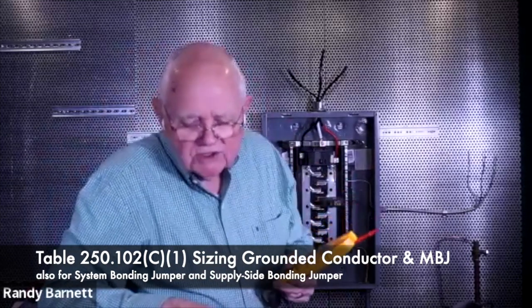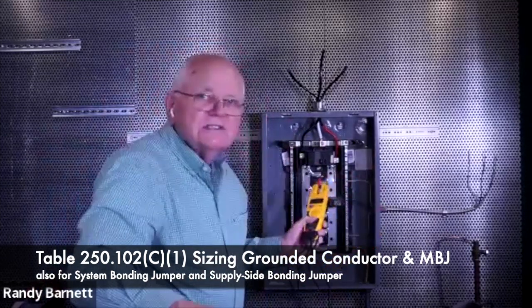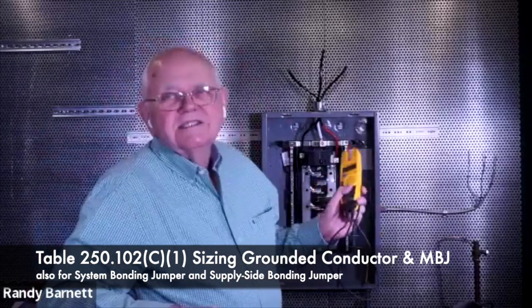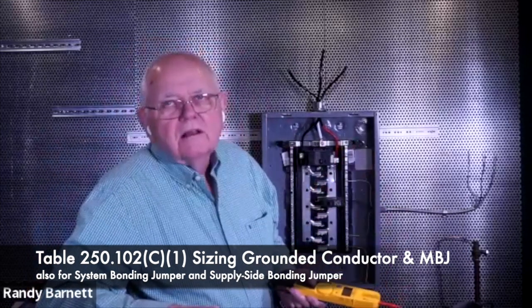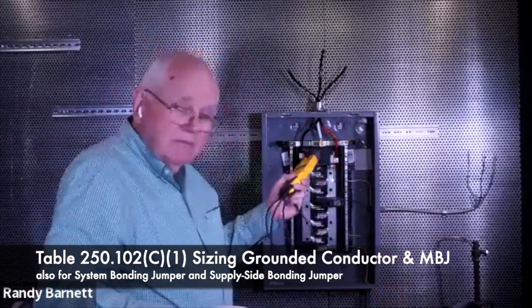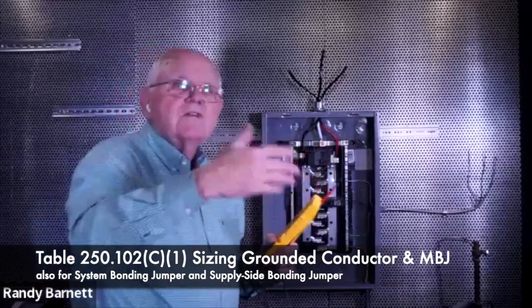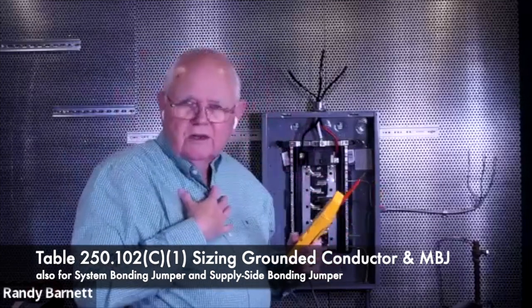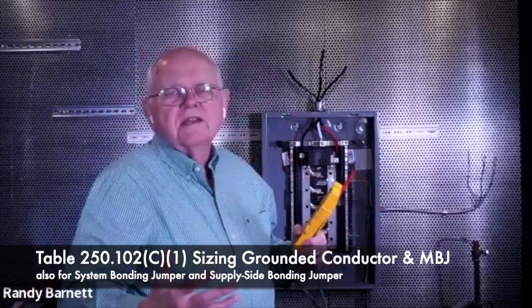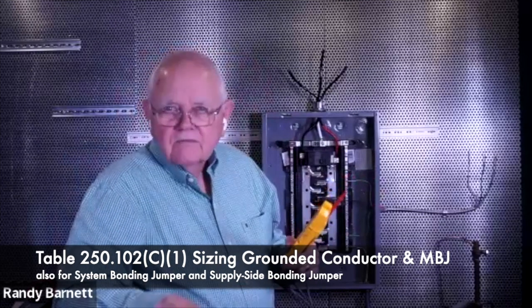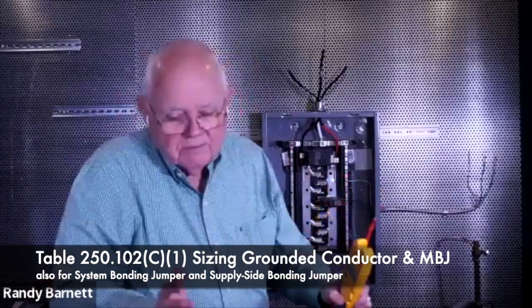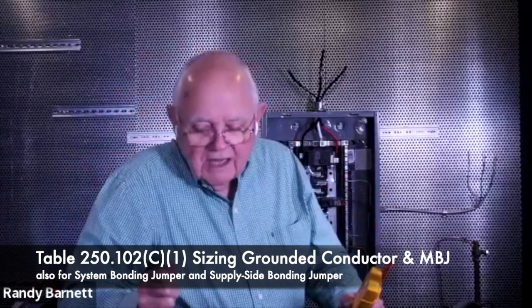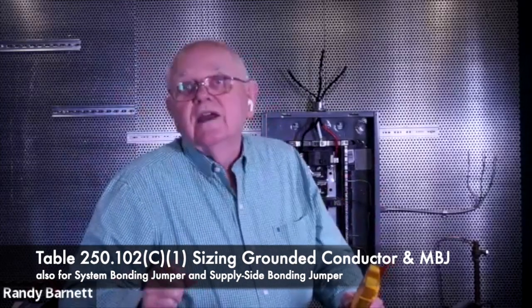The system bonding jumper, we don't have a system bonding jumper in here. Why? Because it's not a separately derived system. If it's a service, it's a main bonding jumper. If it's separately derived coming from another source, say we own the transformer, typically a lot of commercial industrial applications, right? Then in that case, we're going to install a system bonding jumper. And the supply side bonding jumper. Well, we don't have the supply side bonding jumper in the service either. We'll take a brief look at some of the requirements for separately derived systems as well.